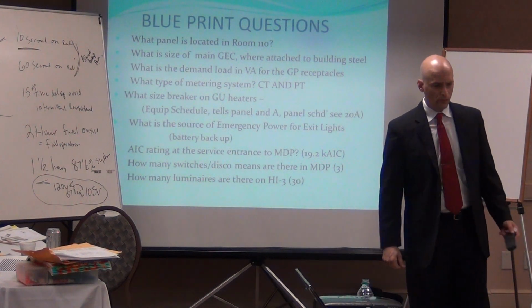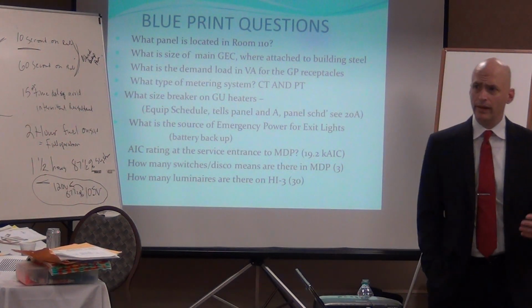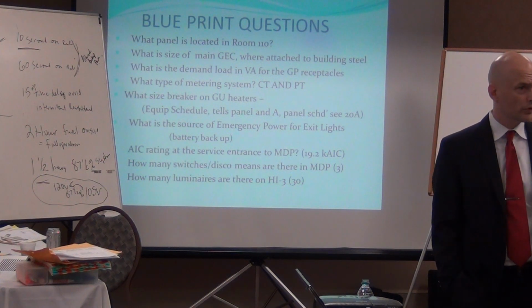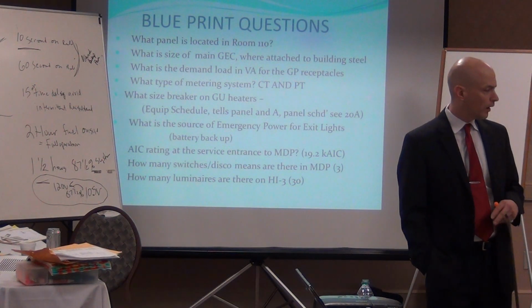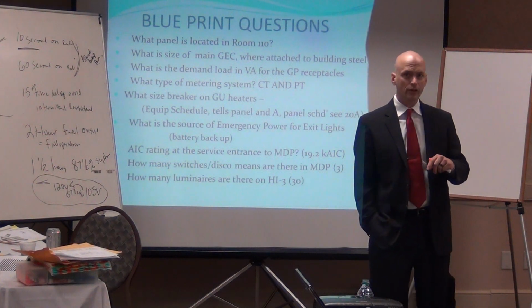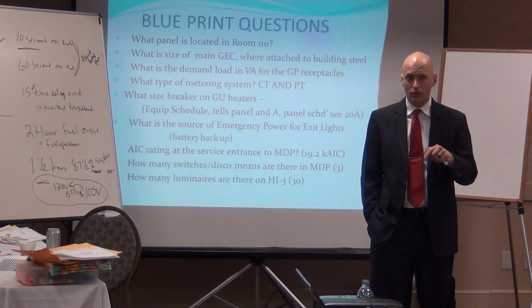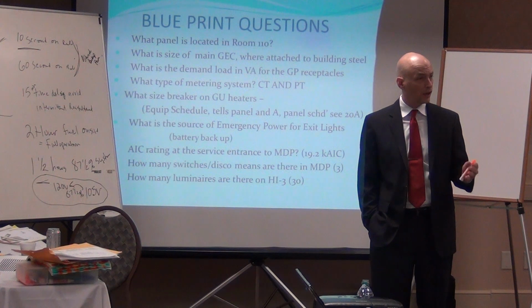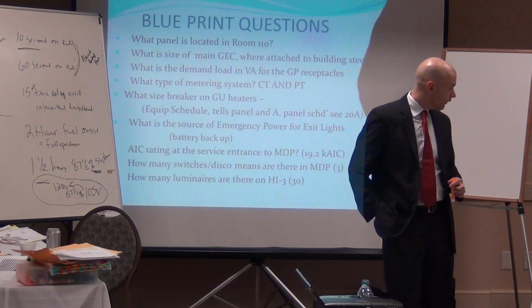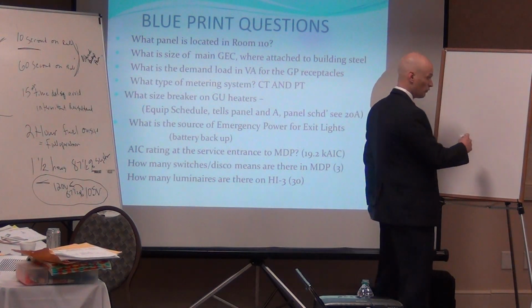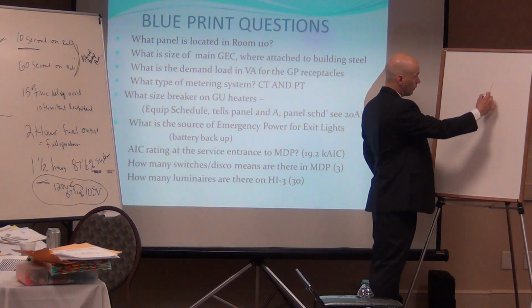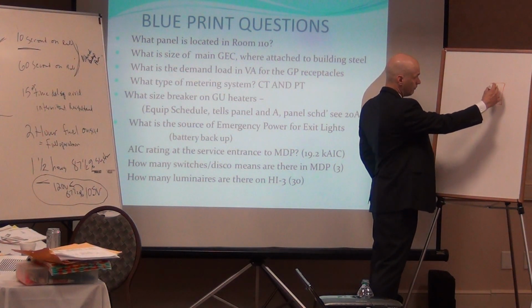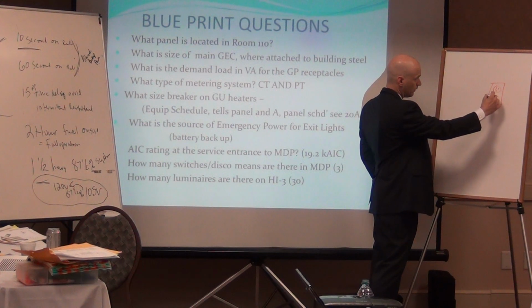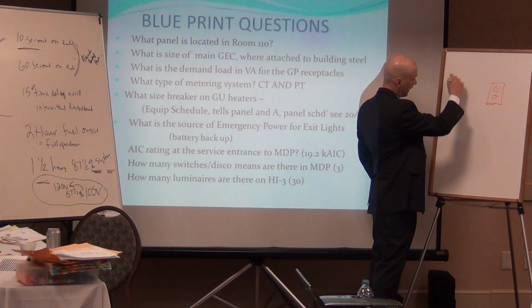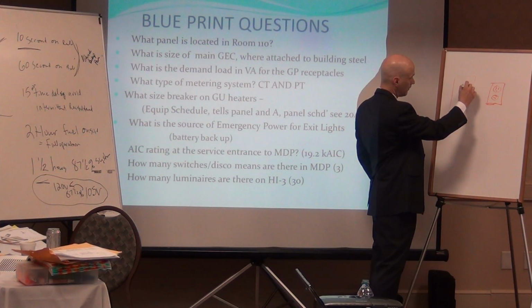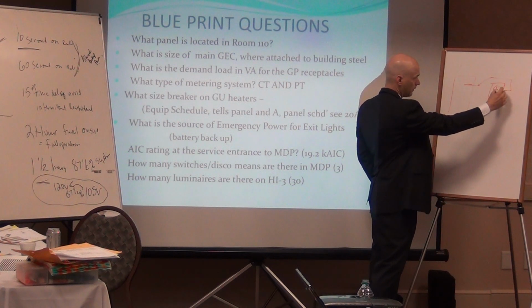You've got to be careful, a neutral, just because a wire is white or gray, doesn't necessarily mean it's a neutral. All white and gray wires are grounded conductors, conductors we intentionally connect to ground, but they carry current. A grounded conductor, they don't use the term neutral very often, because if you look at a single pole 20 amp circuit going out to a receptacle from a panel, you've got your hot coming out, your line side.